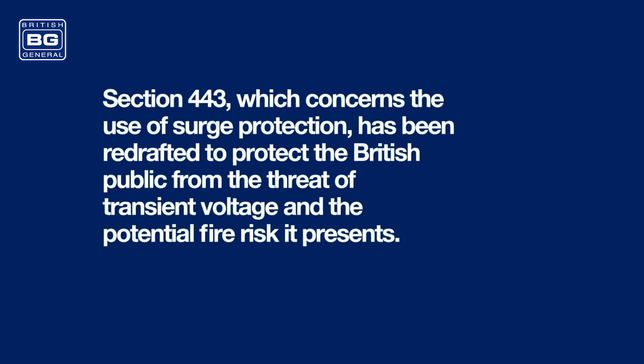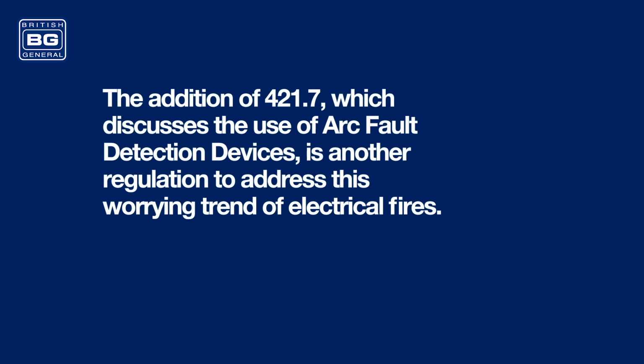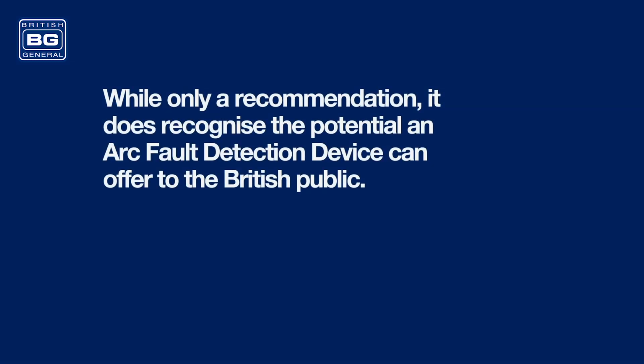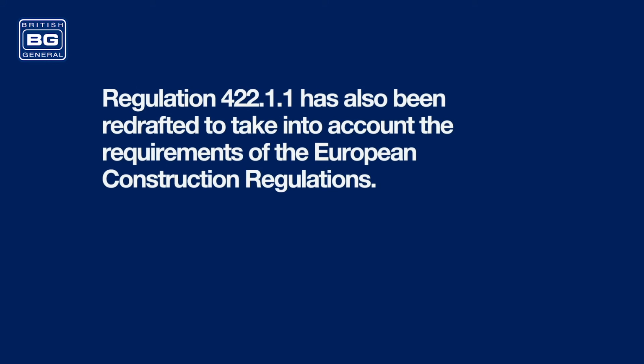Section 443, which concerns the use of surge protection, has been redrafted to protect the British public from the threat of transient voltage and the potential fire risk it presents. The addition of 421.7, which discusses the use of arc fault detection devices, is another regulation to address this worrying trend of electrical fires. While only a recommendation, it does recognise the potential an arc fault detection device can offer to the British public. Regulation 422.1.1 has also been redrafted to take into account the requirements of the European construction regulations.